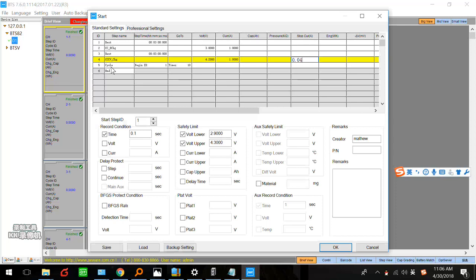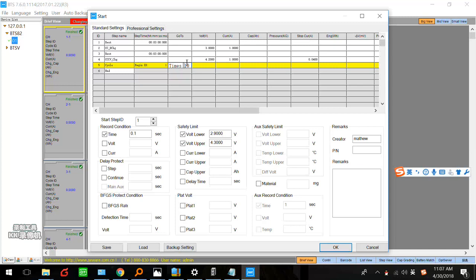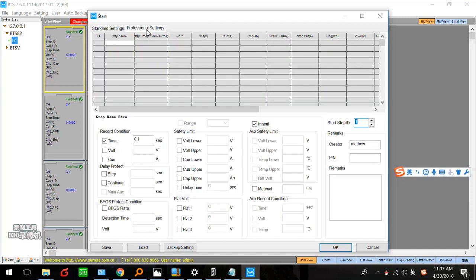Next, set a cycle step. Set the cycle beginning ID to one, and set the cycle count — maybe 10 cycles. If you just want to test the capacity, two cycles is enough. But if you want to test the cycle life and the rated cycle life is 500 or 1000, you can set that accordingly. For this demonstration I'm just testing capacity so I'll set it to two cycles. This is a very easy setup for lithium battery capacity testing.